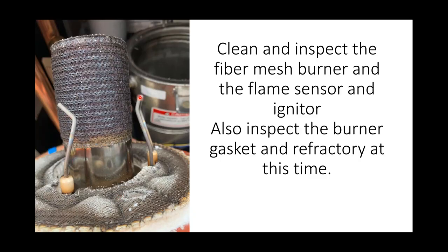Check the condition of the flame sensor and the igniter. Make sure that they're within the proper gaps, especially the igniter. As they get further and further apart, you can get hard light offs, delayed ignition, some noise on light off, and it can usually be attributed to the gapping on the flame sensor.